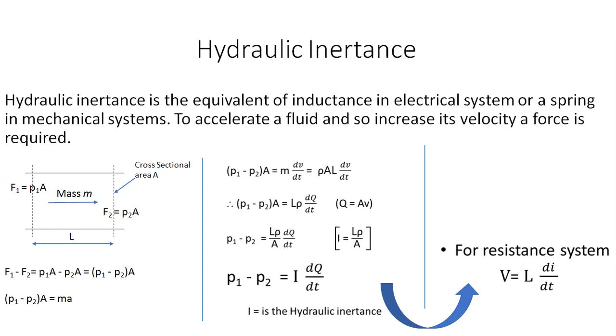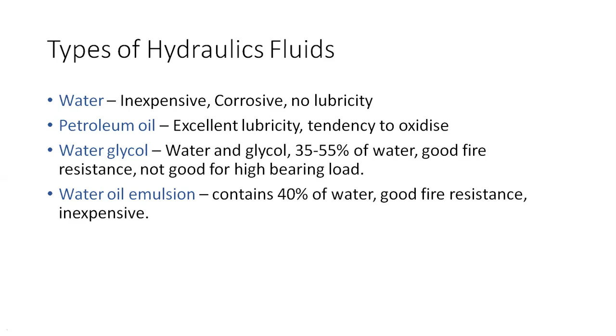So what are the types of hydraulic fluids? Water, petroleum oil, water glycol, and water oil emulsions. Water is inexpensive, but it has corrosion and no lubricity. Petroleum oil has excellent lubricity but a tendency to oxidize. Water glycol has 35 to 55 percent water, good fire resistance, but is not good for high bearing load. Water oil emulsion contains 40 percent water, with good fire resistance, and is inexpensive. So this is about the types of hydraulic fluid.